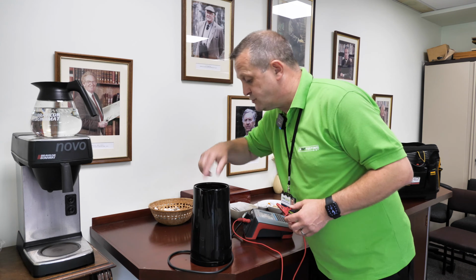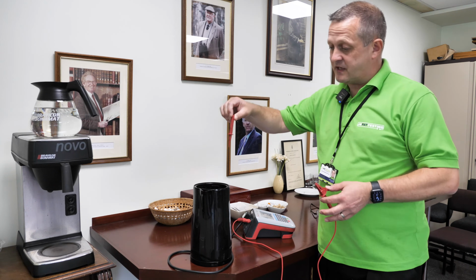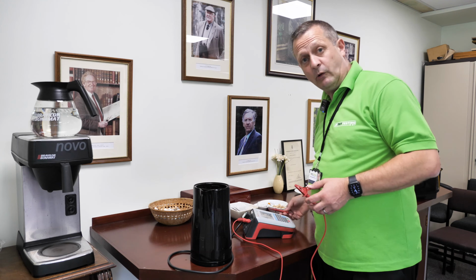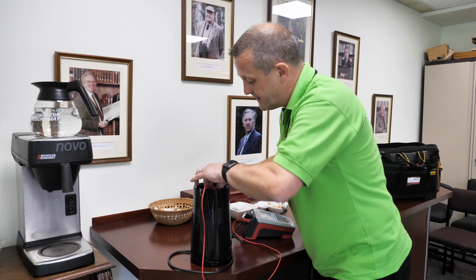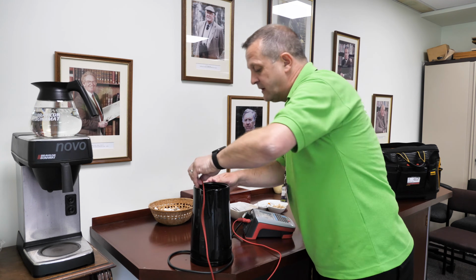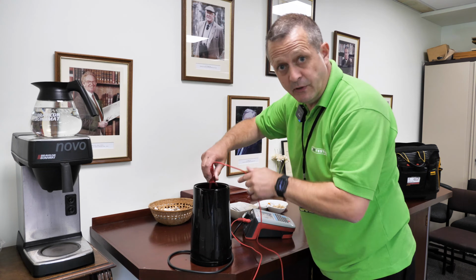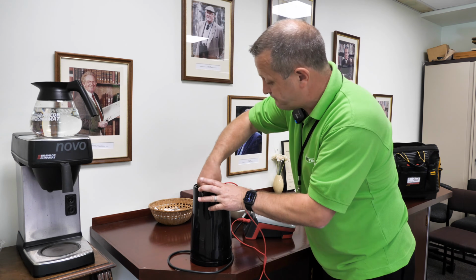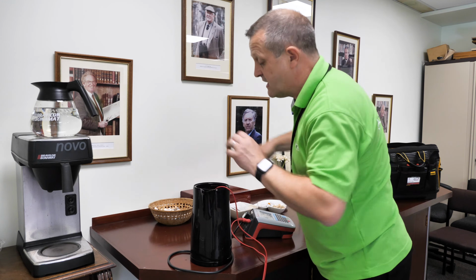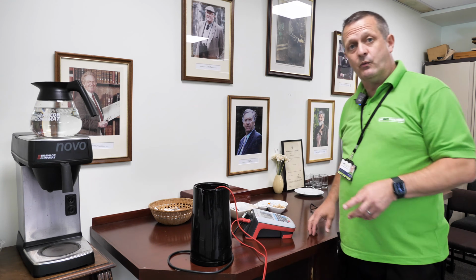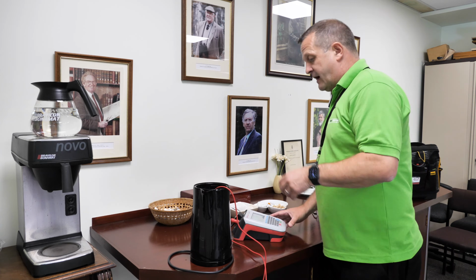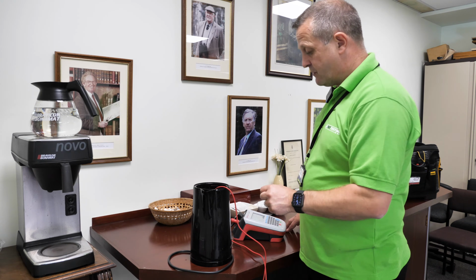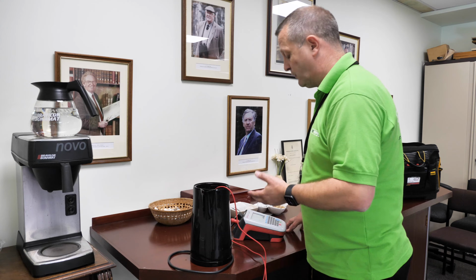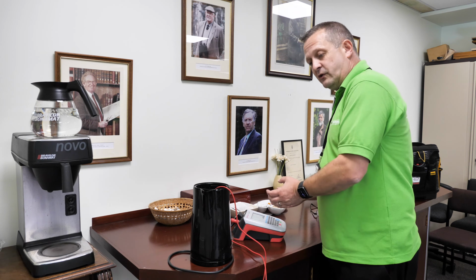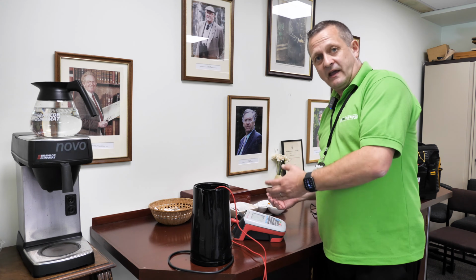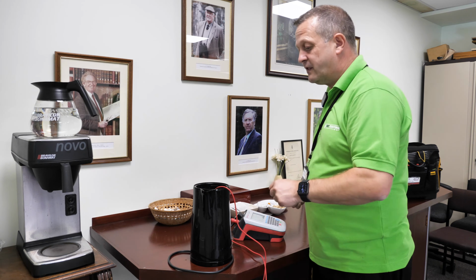Some kettles like this just have the flat base, and if that was the case you just push the prong down onto the metal base, but I'm just going to use here. One thing you need to be a little bit conscious of with kettles is the build-up of lime scale. You also need to make sure that the interior of the kettle is dry, otherwise that will affect your earth readings. But lime scale will also affect, this is a relatively clean kettle, but if you get a failure with a kettle, what I would suggest is just check the lime scale.